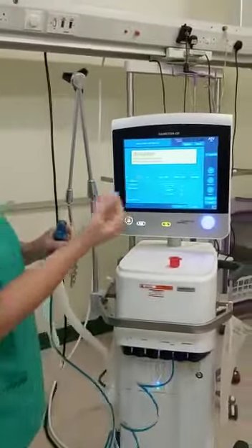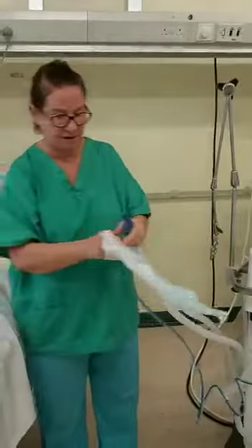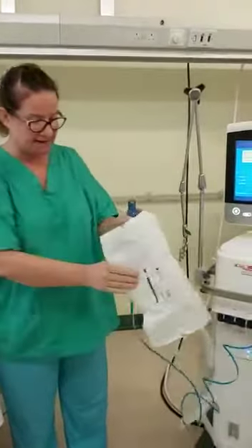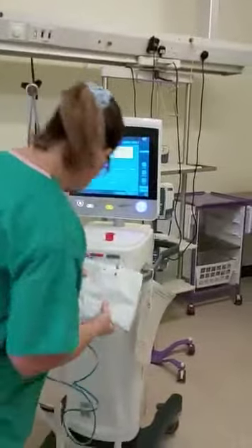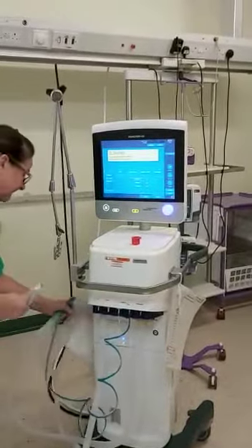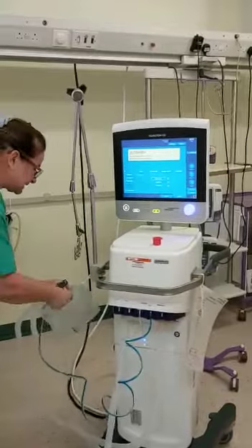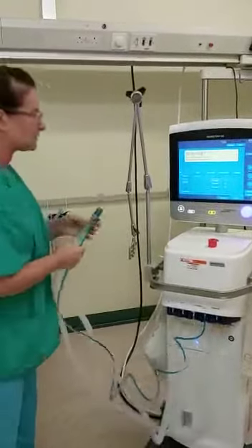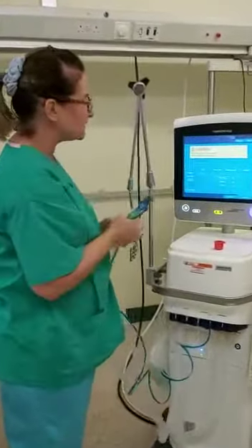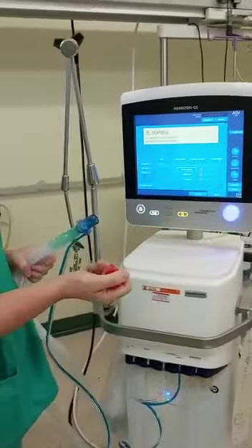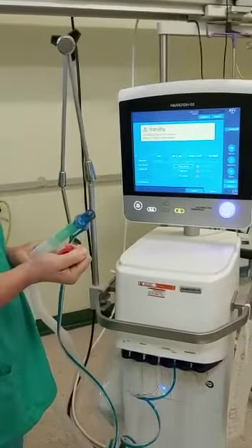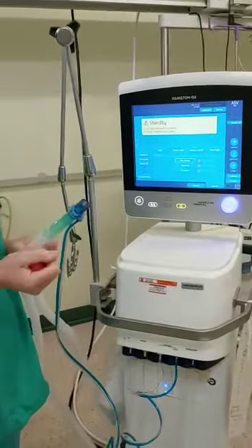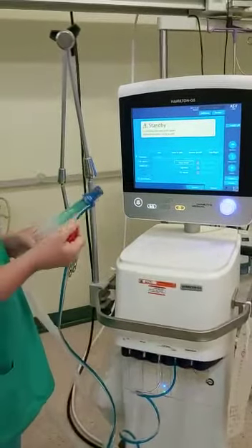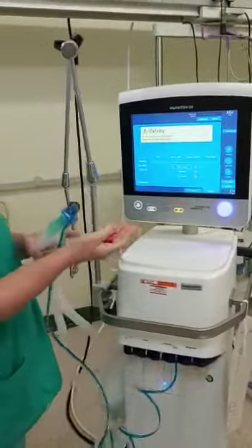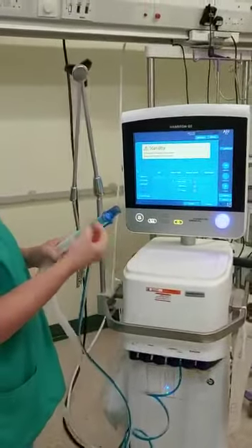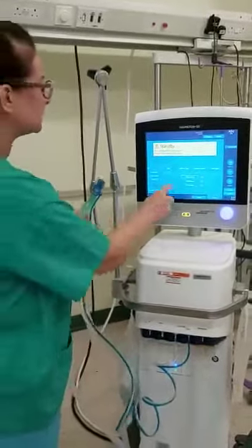So that little white adapter can now come off, go inside the packet that our respiratory valve came in, and that can go onto the side of the ventilator in the plastic wallet. So that's ready for when we need it. So the next one we're going to do is the tightness check. You can use the red cap over the end when it tells you to tighten the patient's system. You do need to press it quite tight. If it fails ever, you can try putting a glove on your hand and sticking your hand over the end, which often will make a tighter seal.